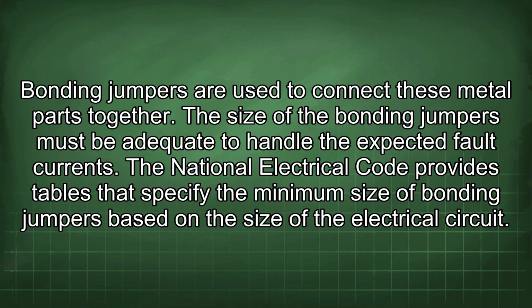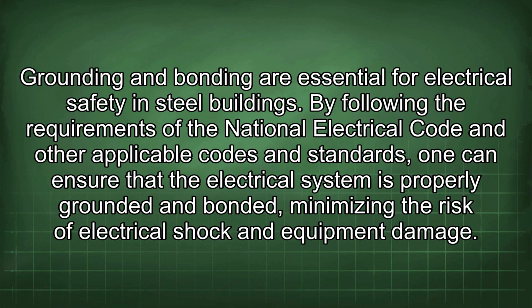The size of the bonding jumpers must be adequate to handle the expected fault currents. The National Electrical Code provides tables that specify the minimum size of bonding jumpers based on the size of the electrical circuits. Grounding and bonding are essential for electrical safety in steel buildings. By following the requirements of the National Electrical Code and other applicable codes and standards, one can ensure that the electrical system is properly grounded and bonded, minimizing the risk of electrical shock and equipment damage.